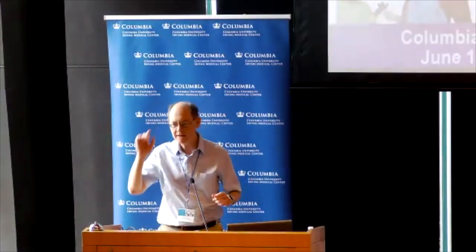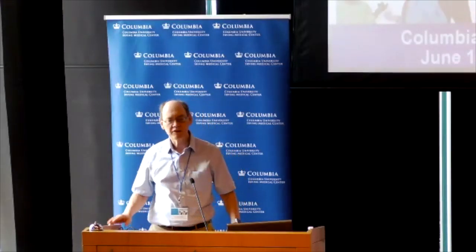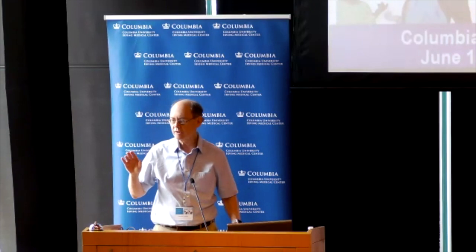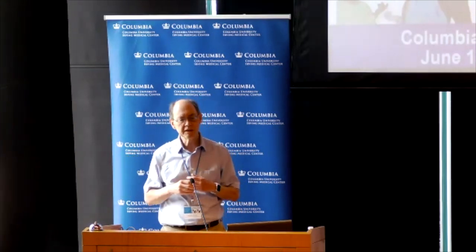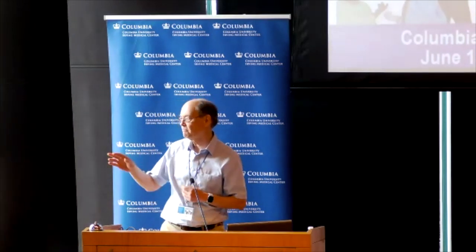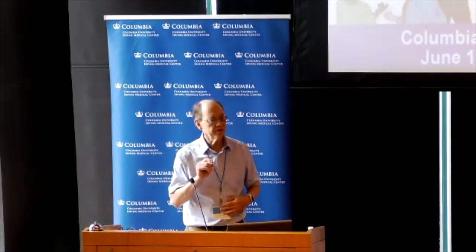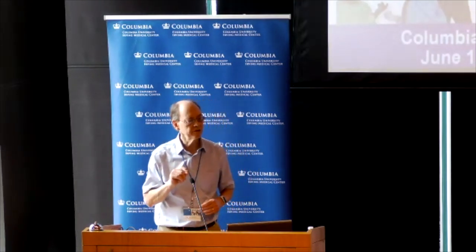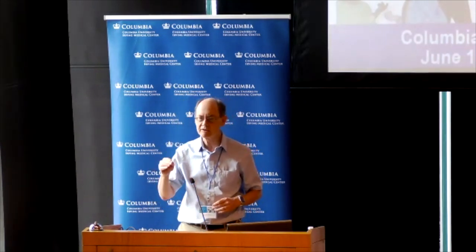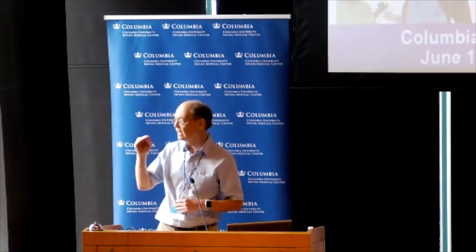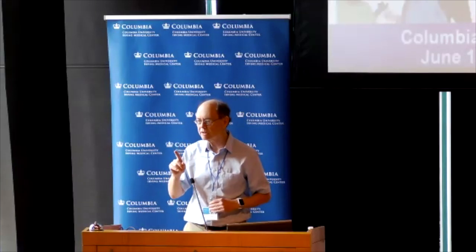And first, I may be preempting something Ed's going to say in a minute, but thinking about what the ACGIH standard says, it talks about millijoules per square centimeter, not microwatts per square centimeter. And that is an important distinction because people move around. They don't stay in the same position. They don't stand directly under the light for 8 hours to get the dose that you would expect based on an irradiance measurement. And that's really, really important.